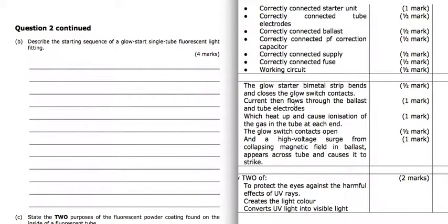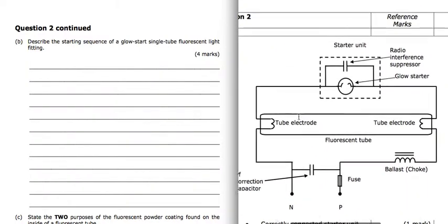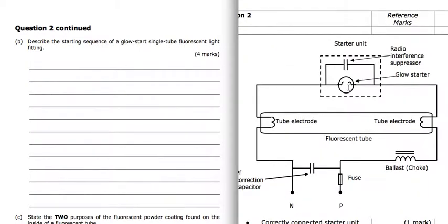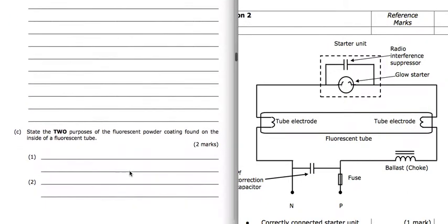So we've got that explanation there. Heat up, glow switch contacts open, high voltage, causes it to strike. So it's all about this glow starter opening, this choke collapsing, and us getting a high voltage on the electrodes.